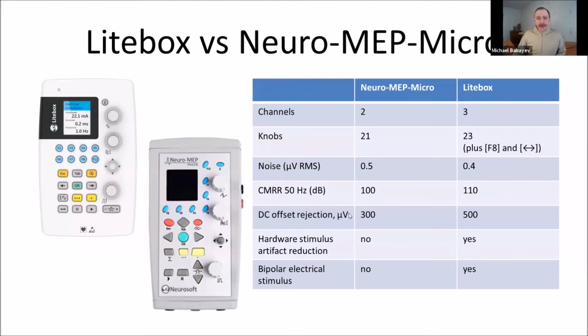Also, you can see very important characteristics, very important parameters of the devices. One of them is the internal noise. Here it is noise in microvolts, RMS, root mean square. And you can see Neuro-MEP-Micro has noise 0.5 but Litebox has 0.4. But in reality, we get near 0.3. So it's a very, very low level.